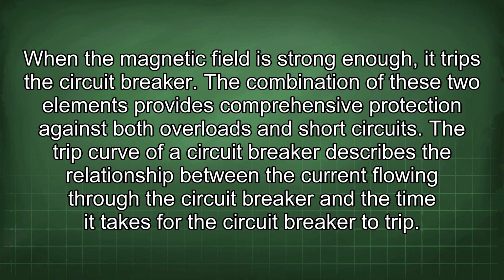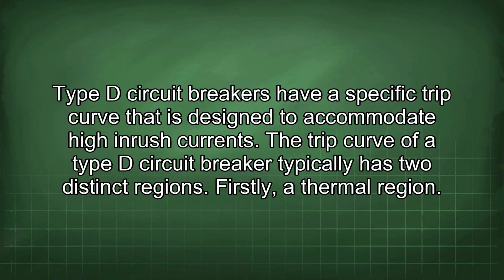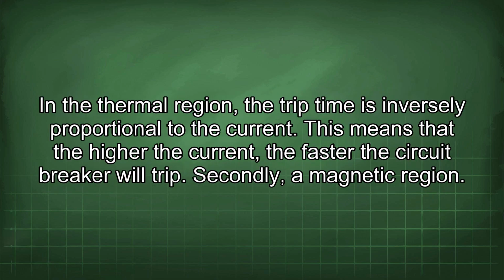The trip curve of a circuit breaker describes the relationship between the current flowing through the circuit breaker and the time it takes for the circuit breaker to trip. Type D circuit breakers have a specific trip curve that is designed to accommodate high inrush currents. The trip curve of a Type D circuit breaker typically has two distinct regions. Firstly, a thermal region. In the thermal region, the trip time is inversely proportional to the current. This means that the higher the current, the faster the circuit breaker will trip.